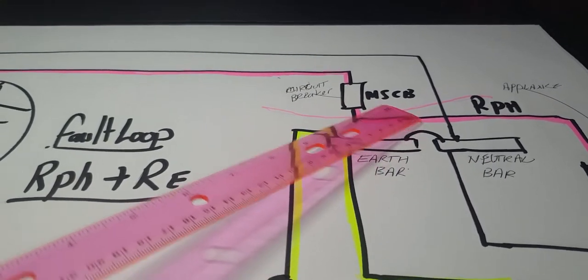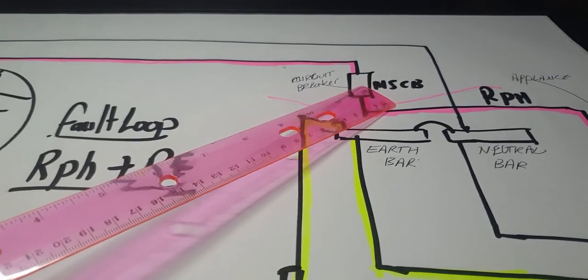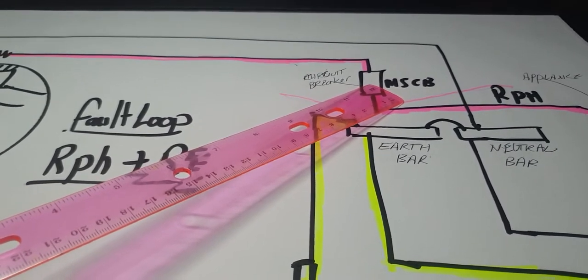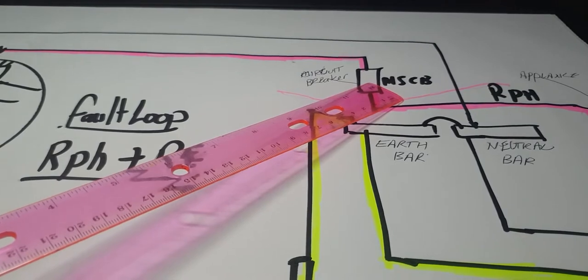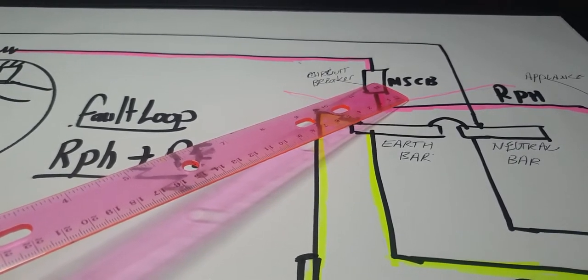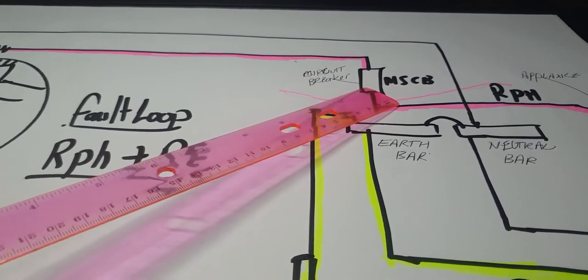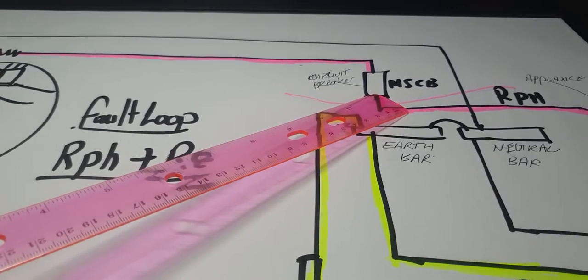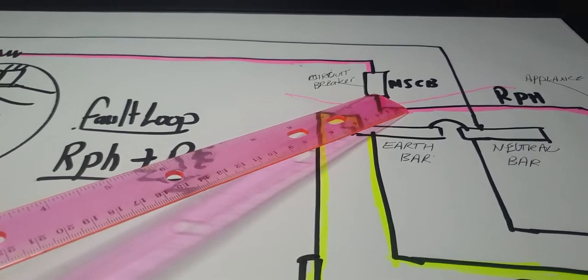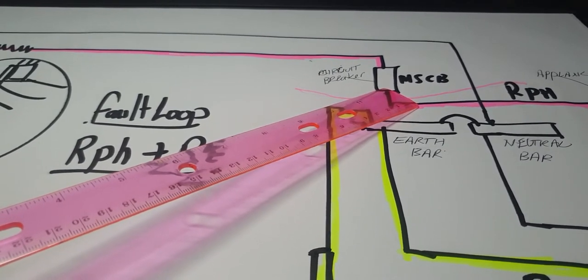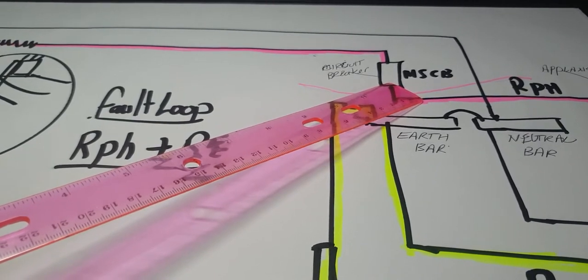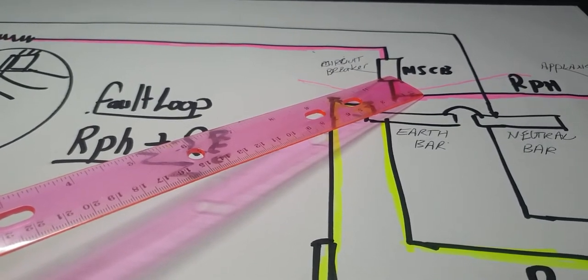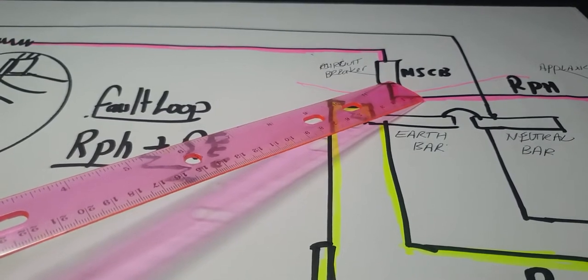There is a difference between using a circuit breaker and a fuse. HRC fuses, being made of ceramic, have a very large kA rating because they don't melt very easily. That's why you'll see a lot of service fuses with ceramic fuses. Circuit breakers have mostly 6 kA minimum for Victoria under the SIR book, but each state travels differently. Some have a main switch as a service fuse in Tasmania and South Australia, with a ceramic fuse in the holder on the main switchboard to protect the circuit coming into the house, then circuit breakers protect all the sub circuits.